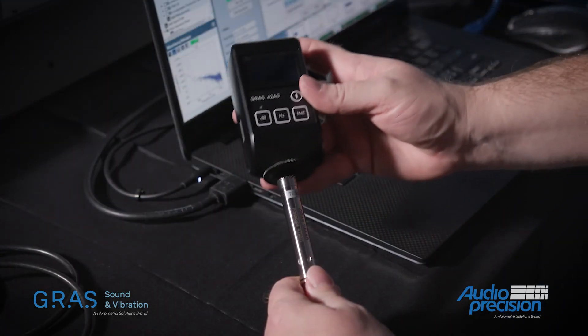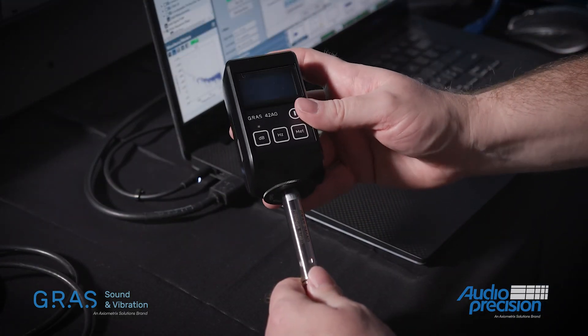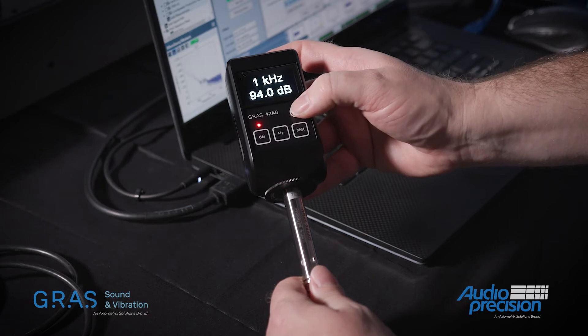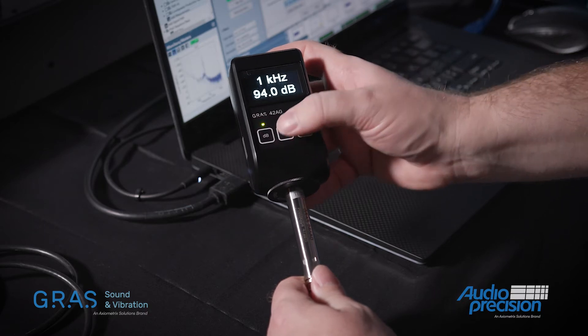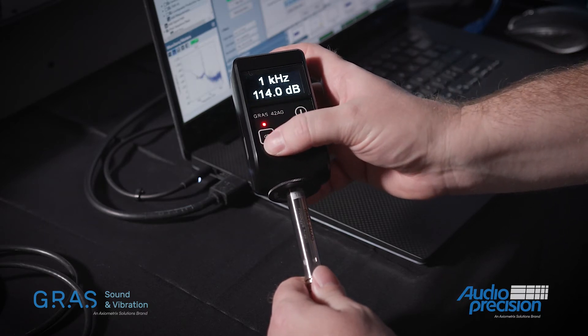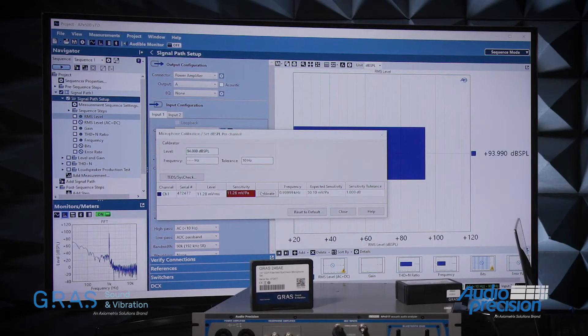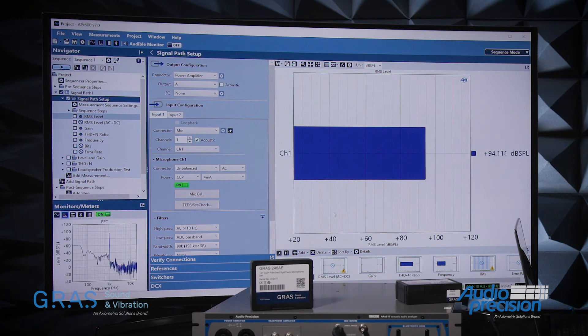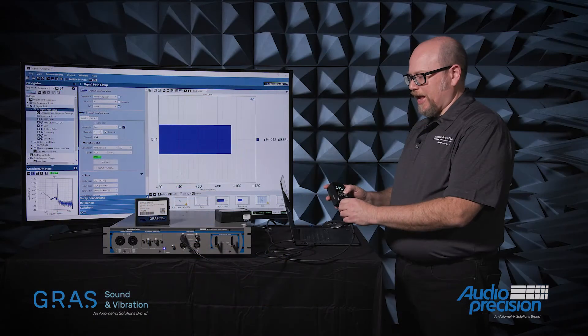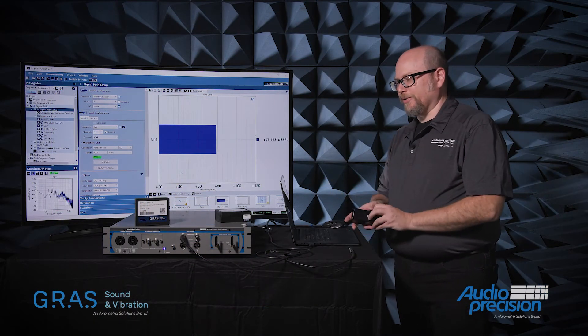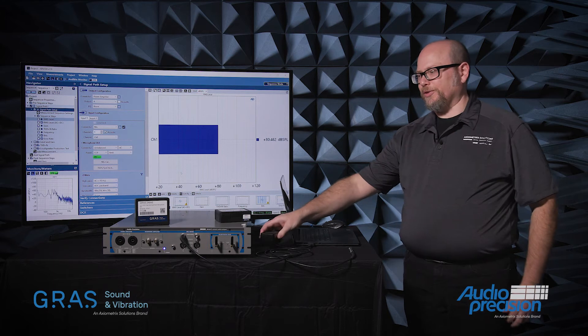I place the microphone in the acoustic calibrator, turn that on, and capture the sensitivity of my microphone. That is certainly a classic way to do it and a pretty reliable way to do it.